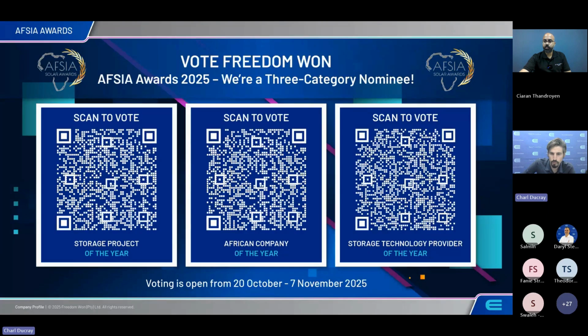I see Rocco popped through a question here, I see it's not already answered but I'll reiterate it. Rocco asked what's the smallest size you can start off on, and we've confirmed it's 217 kilowatt hours with a 6M1T frame that's fully populated with the megaTower plus battery module stack. We have individual modules that make up the stack, each of which is 36 kilowatt hours, so 6 of those stacked together in the 6M1T add up to our 217. That 6 setup is required to get to the voltage we want, because those units are set up in series. We don't typically sell it in units lower than the 6 stack, because we found that gives us the voltage required for many of the inverters in that range.